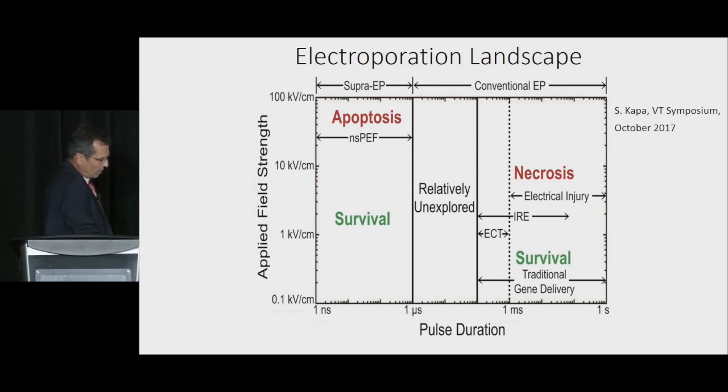This is showing you the impact of the duration of the pulses you are delivering and the voltage you are delivering. Typically, it's very much linked, and if you increase the duration, you will increase the efficacy, of course, with some caveats to that. If you increase the voltage, you will also increase the efficacy, but also with some caveat to that.